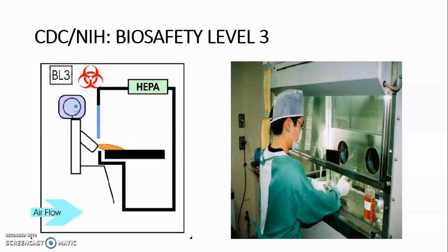Biosafety level 3 contains agents with potential for respiratory transmission that may cause serious and potentially lethal infection. Examples include Mycobacterium tuberculosis, yellow fever virus, hantavirus, and Yersinia pestis (plague). BSL-3 labs require a containment lab with double-door entry, directional airflow, and all work performed in a biosafety cabinet.